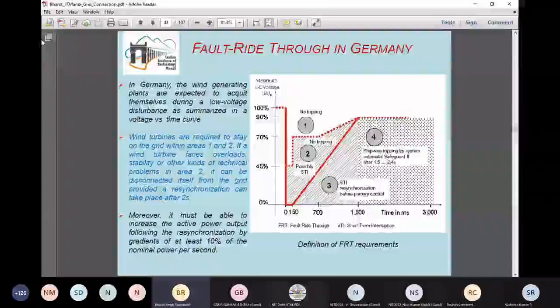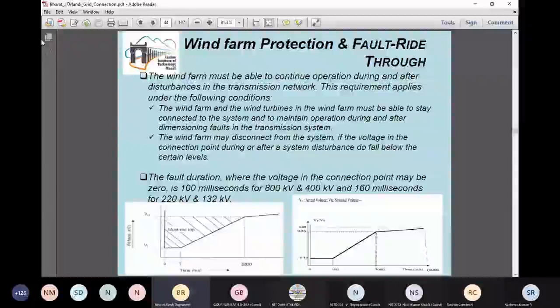The next slide gives us the fault ride-through capability of the Indian grid code. In the right-hand figure, you can see the voltage is 0.15 up to 300 milliseconds, and then the system need not be disconnected. But if the voltage level is below this, the system can be disconnected. Compared to the Indian grid code, the German grid code is very strict. Our Indian grid code gives more flexibility to wind farms or solar farms to get disconnected during abnormal conditions. So this is the fault ride-through capability curve. Next slide, please.